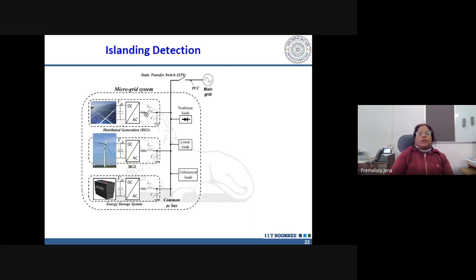Therefore, it is recommended by IEEE standard that we have to de-energize these renewable sources within 2 seconds. And this process of de-energization is not so easy, so we should have a very dedicated islanding detection scheme.